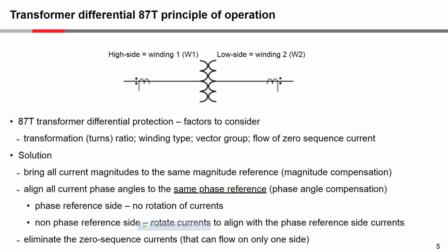So what is the solution to all of this? Well, firstly, it's to bring all current magnitudes to the same magnitude reference, and we call that the magnitude compensation. And then we align all current phase angles to what we're going to call the phase reference. So all have to be aligned to the same phase reference, and this is the angle compensation, phase angle compensation.